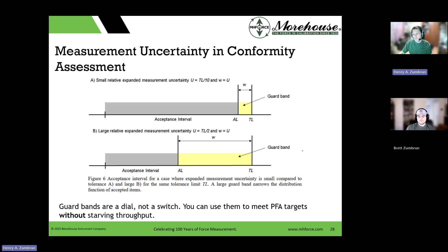And when I say my dream scenario, it's somebody who understands the likelihood and consequence, so they know their actual risk and what they want you to do with their device. They write something like, "Please calibrate as found, manufacturer, 10,000 Newton load cell, serial number, with this readout, in compression only, and issue a pass when using specific risk greater, less than or equal to 2.5%, otherwise fail it." I would say we've never seen a certificate or a purchase order that has been this descriptive, and I would love to see one.